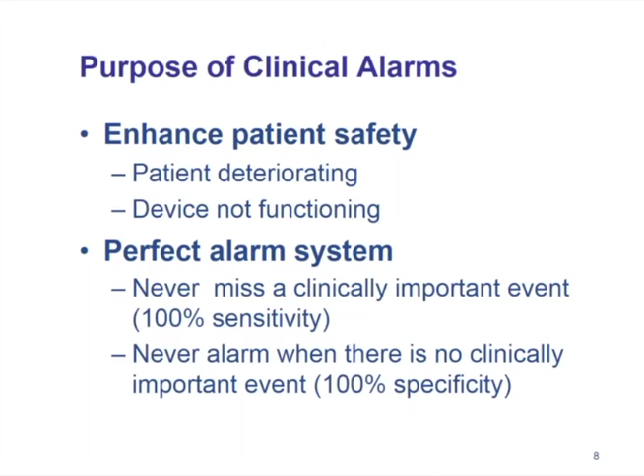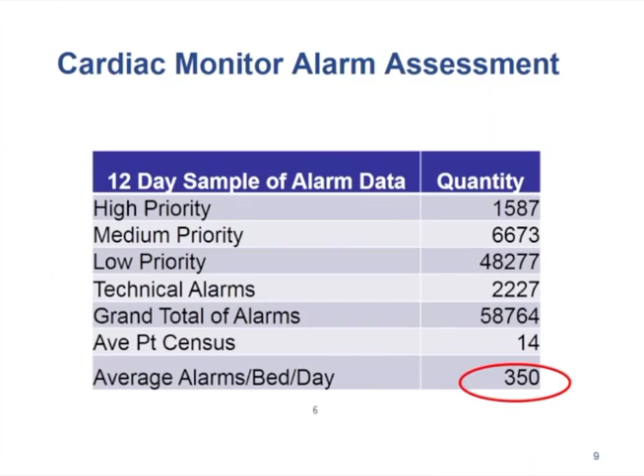At Hopkins, we've been investigating the problem of alarm hazards since 2006. When we started our initiative, we averaged about 350 alarms per bed per day. Monitor alarms occur in a hierarchy, and the bulk of alarms are categorized as low priority. With so many low priority alarms occurring, it's easy to understand how high priority alarms could be missed.